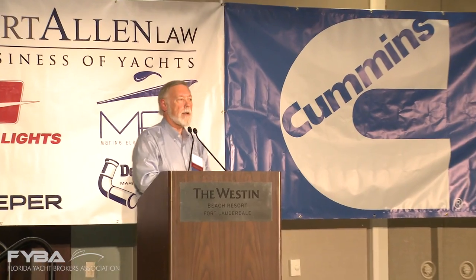The 120 volt side usually is going to be from two different coils in the generator, and those need to be balanced. So we'd like to keep the 120-volt loads relatively the same. But if possible, we'd like to put all the heavy loads on 240-volt. There are a lot of good reasons for this, but without going into really deep detail, it's just generally better for practically everything. So if possible, the heavy loads like air conditioning, hot water heating, anything that's a heavy load should go on the 240-volt side. If you can split those up that way, split the 240-volt loads at the main panel, you wind up with a generator that's more able to carry the heavy loads, and at the same time, there's less wear on the generator. It's a balanced load system.